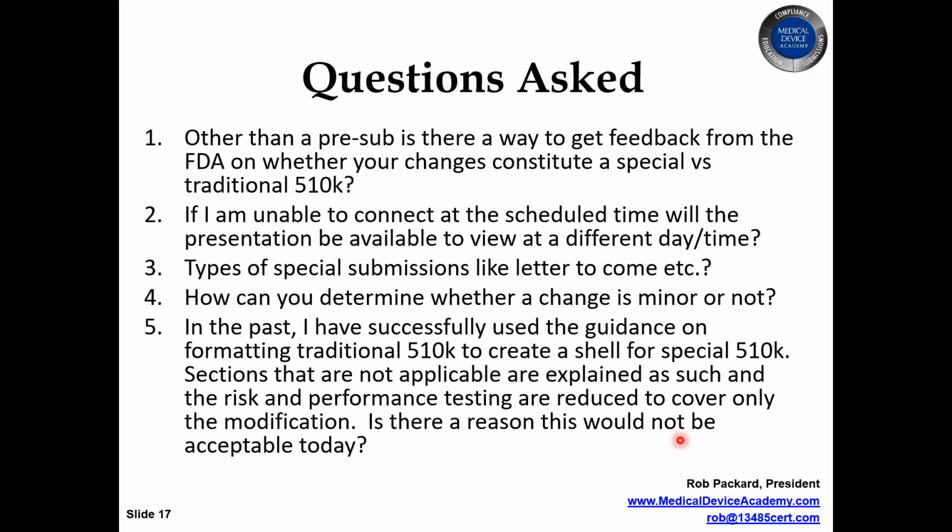The only clarification I think I would make here is the FDA doesn't want full test reports, so they want summaries of test reports. And you might ask in the pre-sub, would this be adequate as a summary, and sort of give them an outline of what information you're going to provide, or is there something additional you want there? But they really don't want full test reports here, so it's a good idea to do a pre-sub just to find out, is this going to be an acceptable summary of the information?